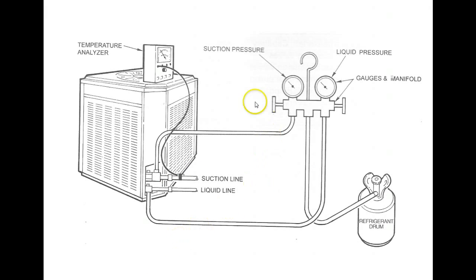When you're charging a TXV metered system, you're going to hook your gauges up in the same manner. Your temperature probe, instead of being put on the suction line, will be connected to the liquid line so that you can measure the temperature of the refrigerant as it exits the condensing unit.